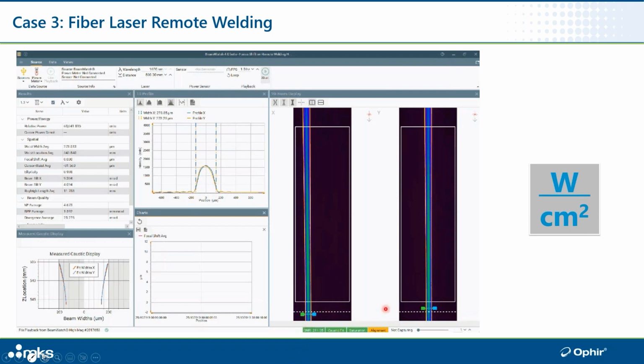There are 2 markers here on each side. One is a blue marker, where the laser focus spot starts out. And then the green marker is a dynamic measurement of the focus shift. So when the beam turns on, it starts here, and then you'll see a dynamic measurement of the focus shift.